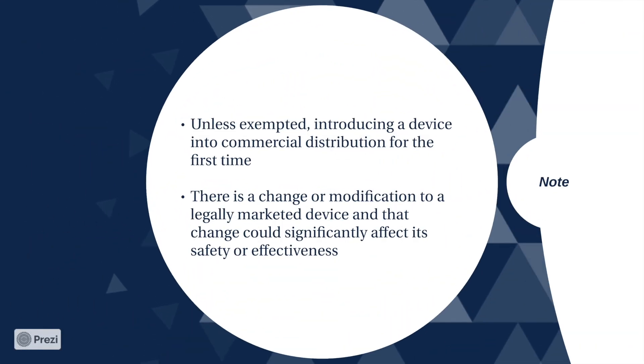When is a 510(k) required? Unless exempted, a 510(k) is required when introducing a device in commercial distribution for the first time, or if there is a change or modification to a legally marketed device that could significantly affect the safety and effectiveness of the device.